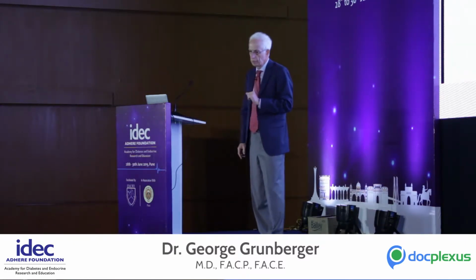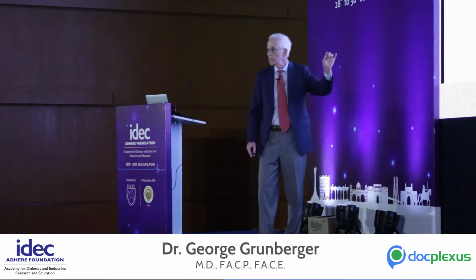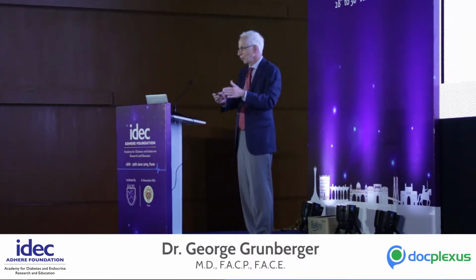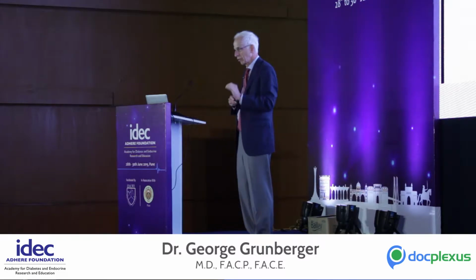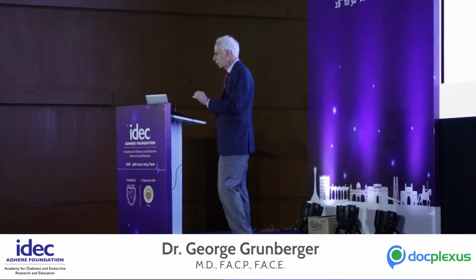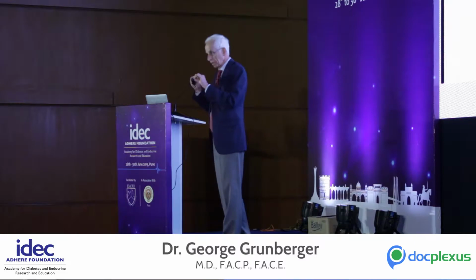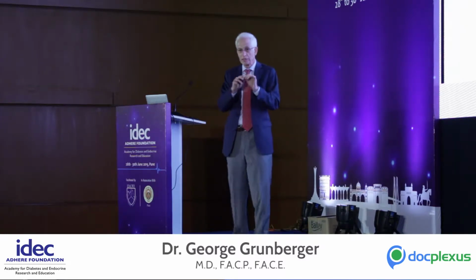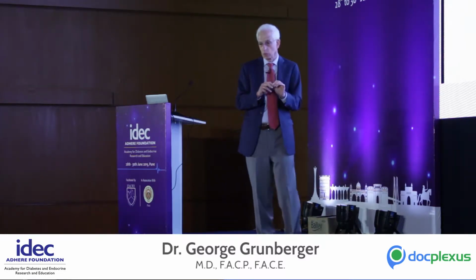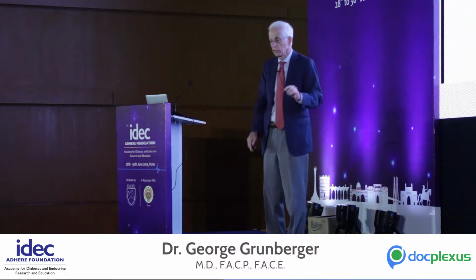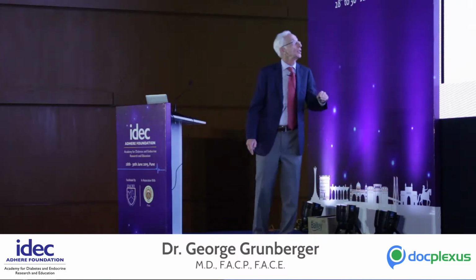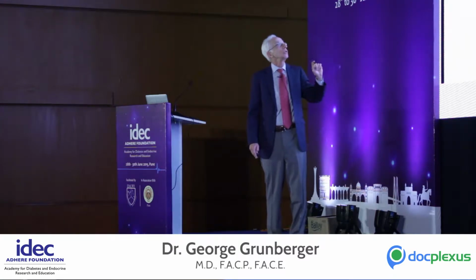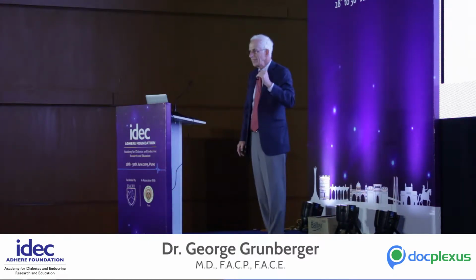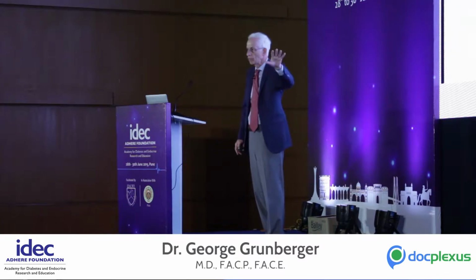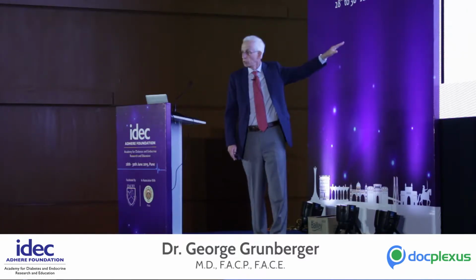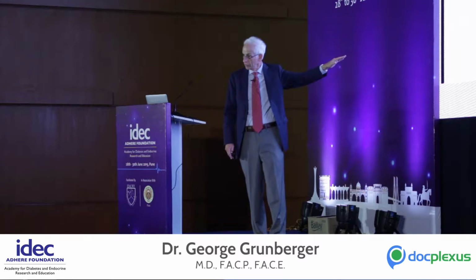What's plotted here on the horizontal axis is MARD, mean absolute relative difference. That is the measure of accuracy. That is, how far are you from the gold standard plasma glucose concentration measured by the Yellow Springs instruments. And on the y-axis, you have the percentage of readings which are more than 20% off. So clearly, the more you get to the lower left, the better you are.